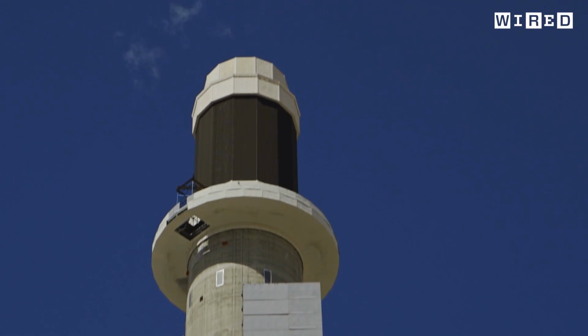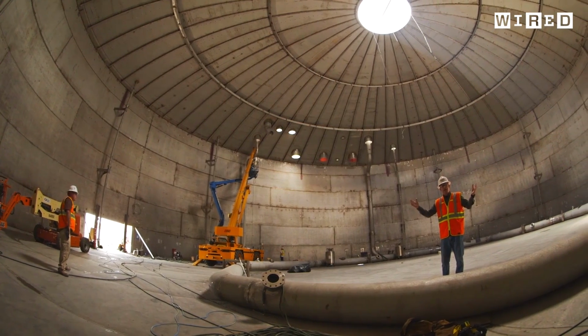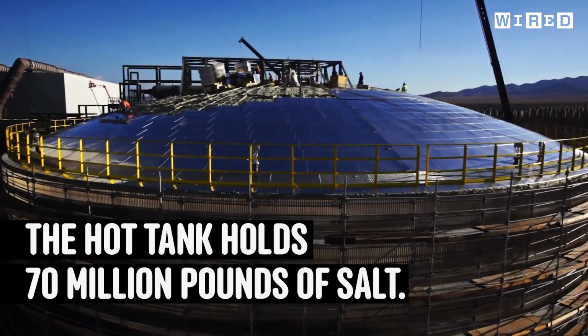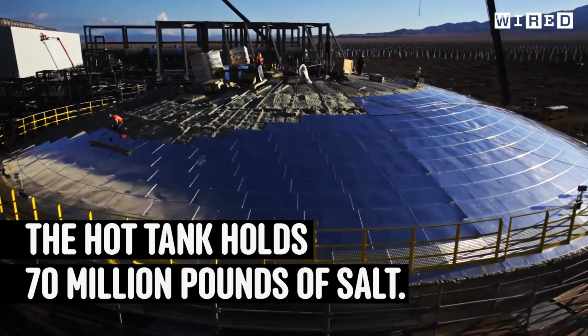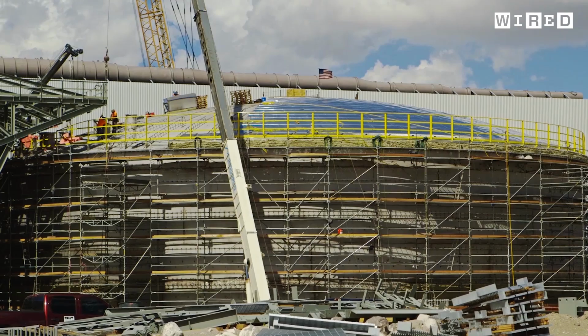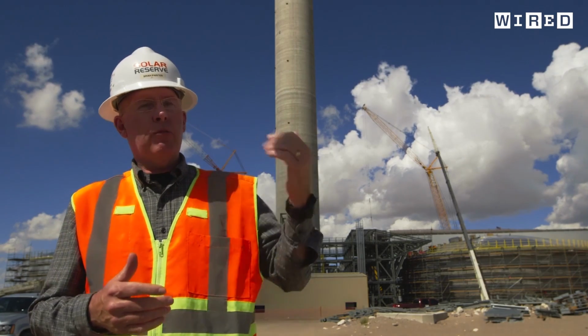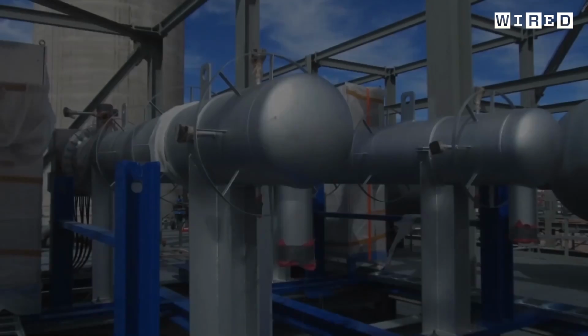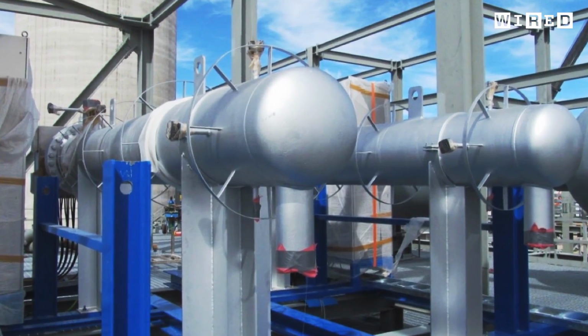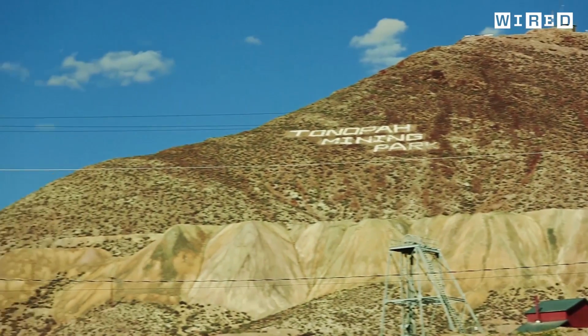Right now we're standing inside of this massive stainless steel tank. The salt in here will be at 1,050 degrees Fahrenheit in a molten state. When we want to make electricity, we'll start up our pumps and pump the hot salt through heat exchangers and superheaters to make steam, which is delivered to the steam turbine to make electricity and deliver it to the utility grid.